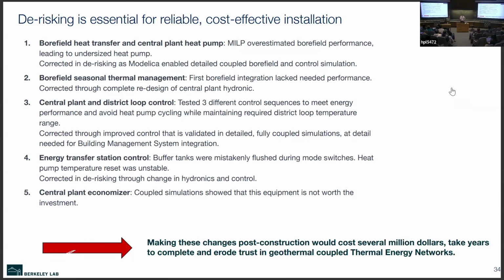Then the bore field seasonal thermal management also didn't work out at first—we didn't achieve the performance we needed from the bore field on an annual basis. That led us to correct it through a complete redesign of the central plant hydronics: all the piping and valving in the central plant shown earlier. The original implementation didn't perform as required.